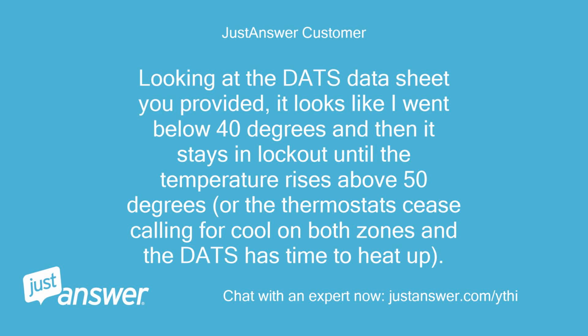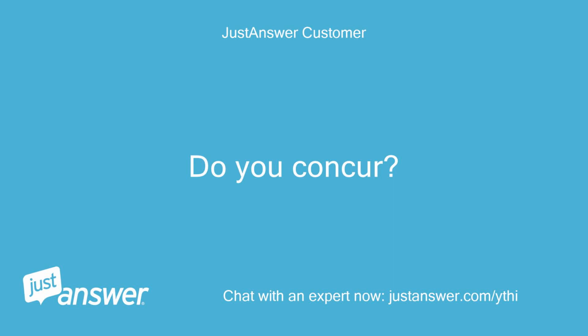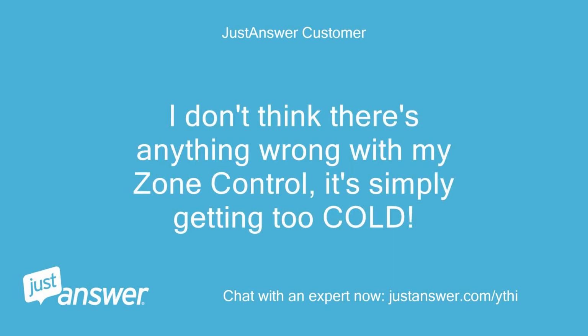Looking at the DATS datasheet you provided, it looks like I went below 40 degrees and then it stays in lockout until the temperature rises above 50 degrees, or the thermostat ceases calling for cool on both zones and the DATS has time to heat up. Do you concur? I don't think there's anything wrong with my zone control, it's simply getting too cold.